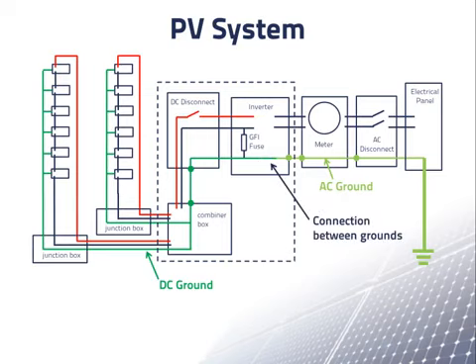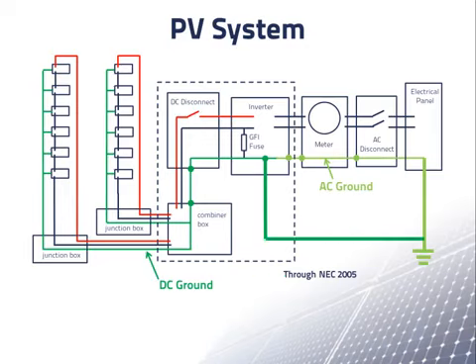The AC and DC grounds are connected to each other in the inverter, which is also where the power from the array is converted from DC to AC. The NEC through the 2005 edition required a wire from the connection point of the DC and AC grounds directly to a grounding rod. You could install a separate grounding rod, or you could make a direct connection to the grounding rod used by the electrical panel. It was usually easier to connect to the electrical panel's grounding rod. However, this was not very feasible in some PV systems.